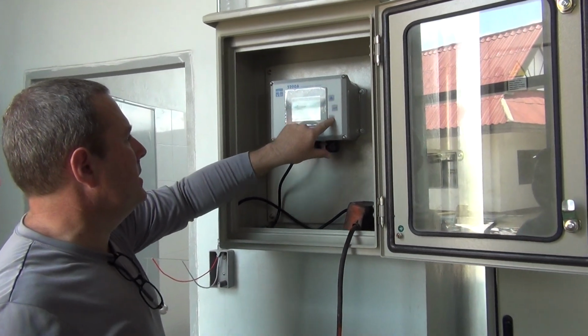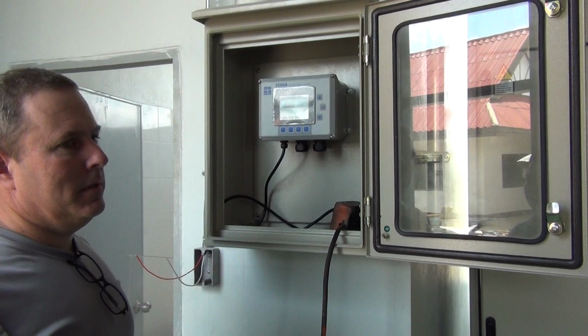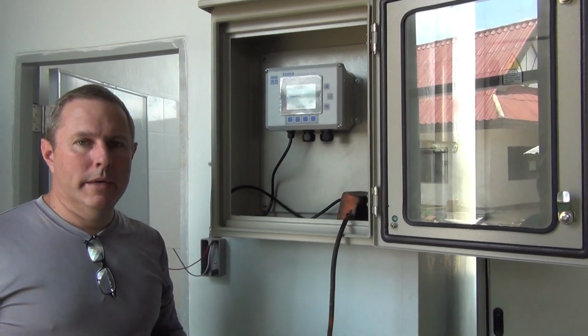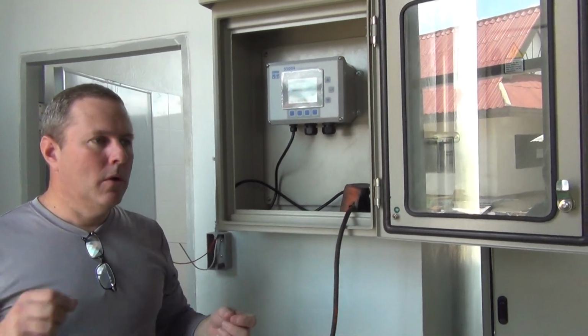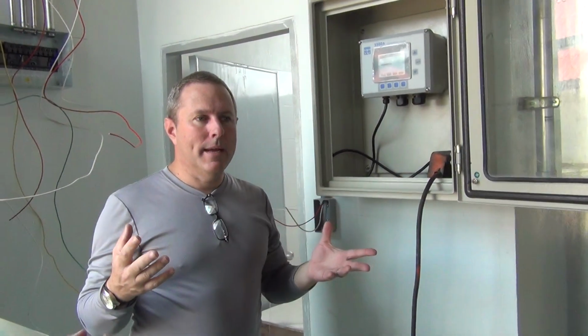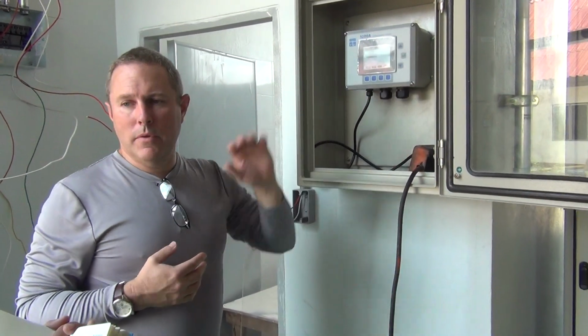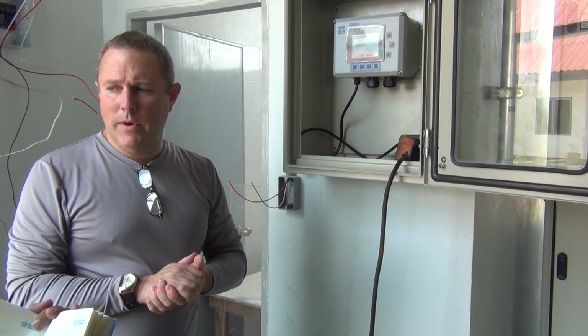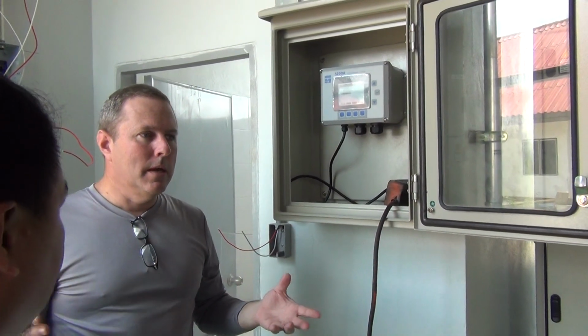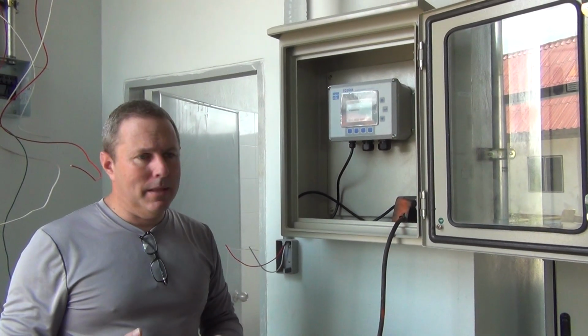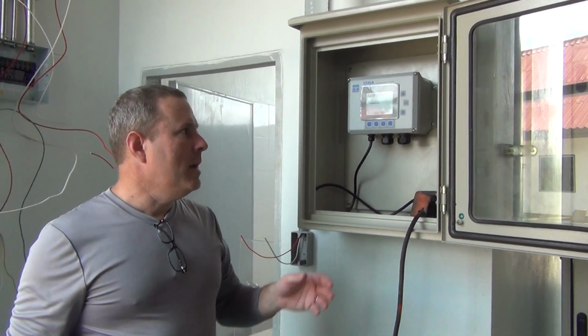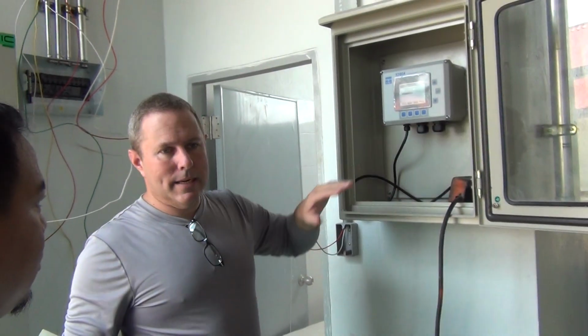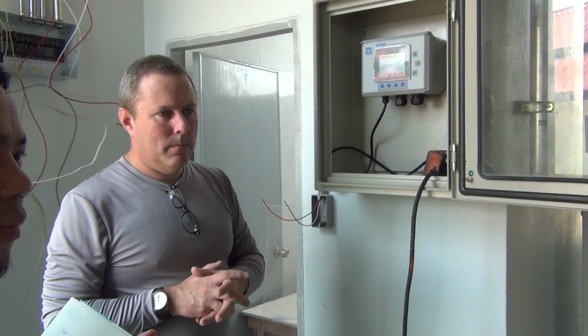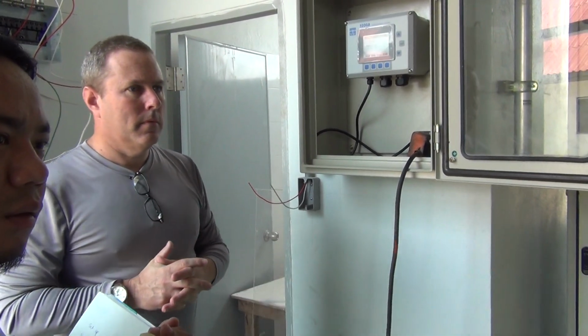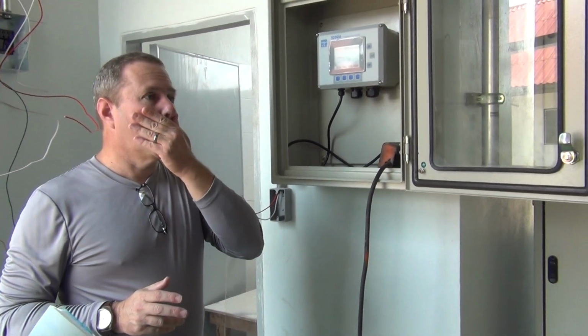The next, relay disabled. If you want to put a siren or a light or a beacon, we can set one of the relays to be controlled by the alarm function so that if somebody is around, they can be notified that there is something that is out of range. So we would set the relay here. Is that something you would be interested in doing? You want to put some light or siren? I think I try silent better.